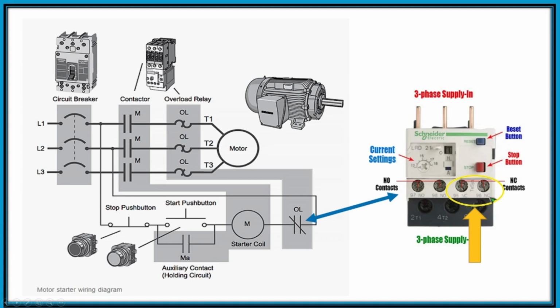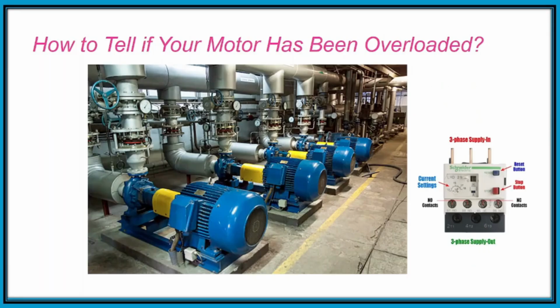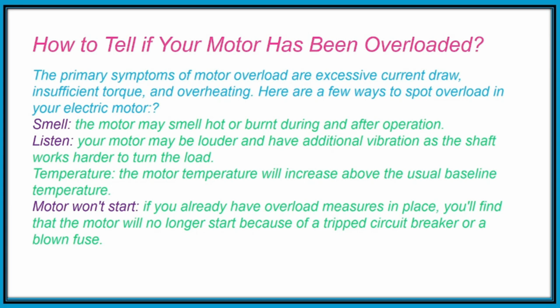If the 95 and 96 is open, even though you are going to reset, that means we have a problem with the overload relay and it needs to be replaced. How to tell if your motor has been overloaded? The primary symptoms of motor overload are excessive current draw, insufficient torque, and overheating. Here are a few ways to spot overload in your electric motor.